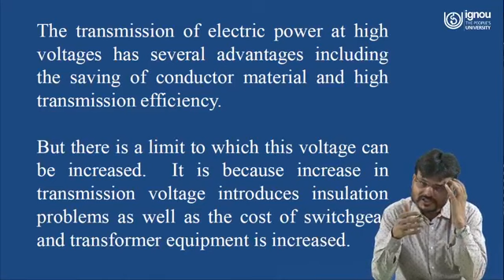The losses as well as the cost of the conductor must be saved, but at the same time if you increase the voltage, the insulation problem comes into the picture. That means there will be some optimization between increasing voltage to save the conductor, and optimizing the cost of the switch gear and transformer. So the choice of power transmission voltage is essentially a question of economics, because there is optimization coming into the picture.